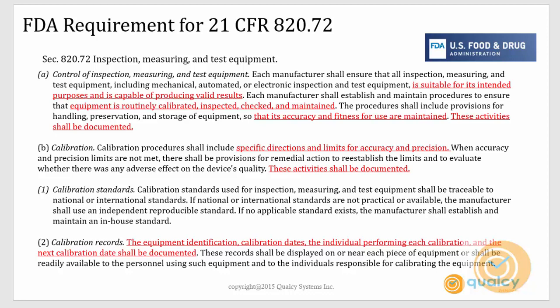So some of these things you can address through the regular scheduled calibrations. Again, when you do the calibration, the equipment identification, calibration date, and the individual performing each calibration shall be maintained, shall be documented. So those are the regulatory requirements. So there is no option for skipping those things, or there is no option for flexibility.